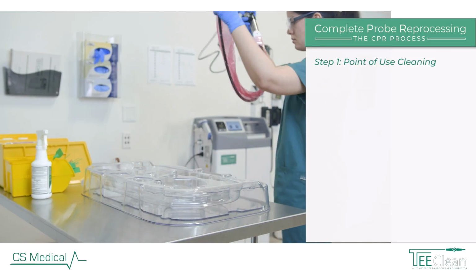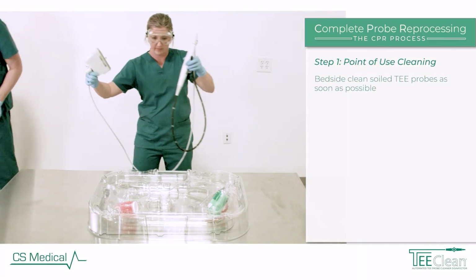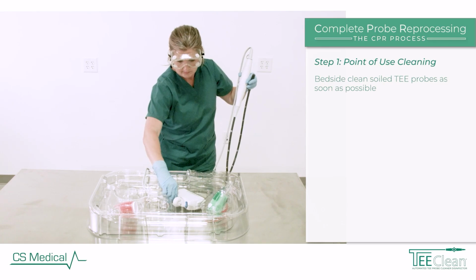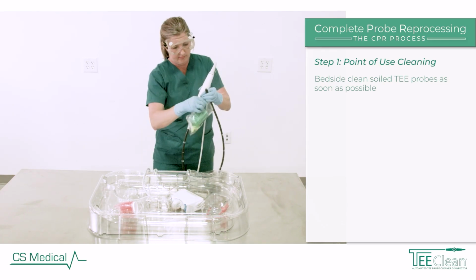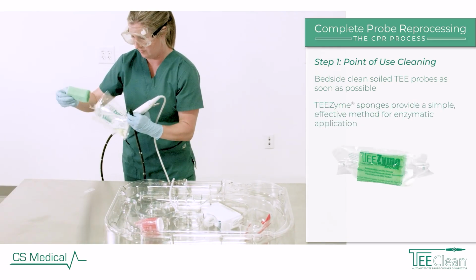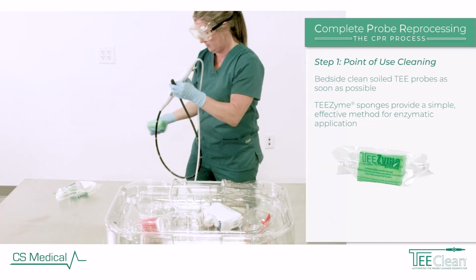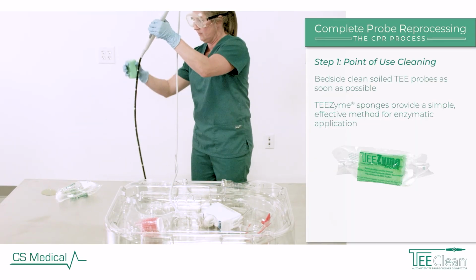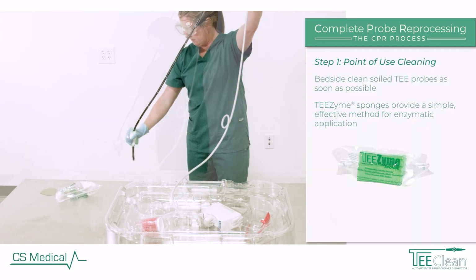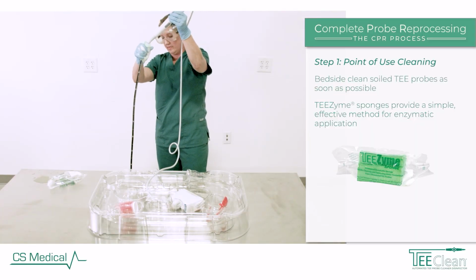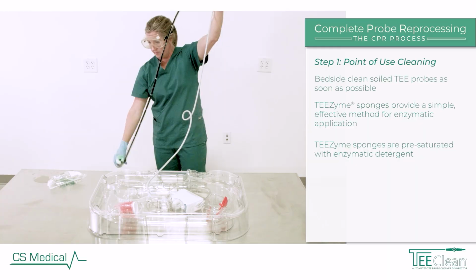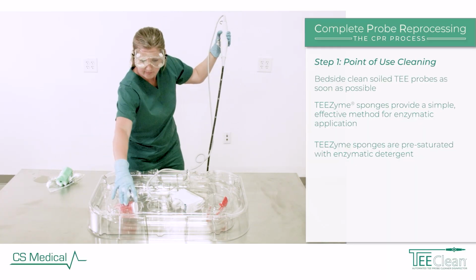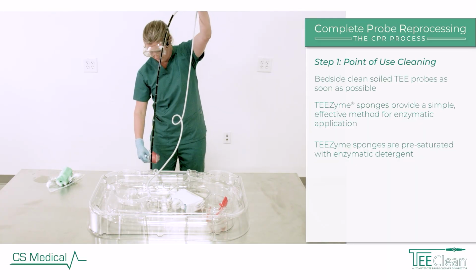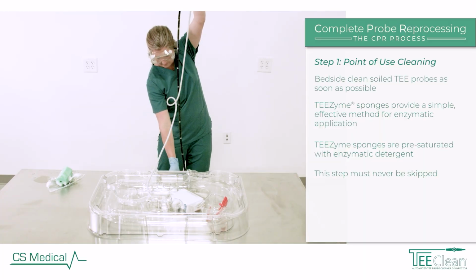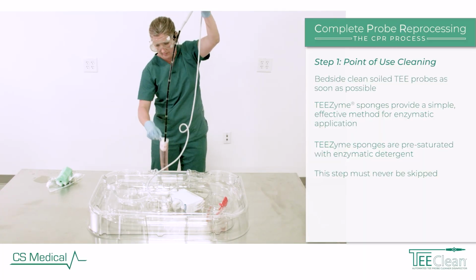Step 1. Point-of-use cleaning. Bedside clean soiled TEE probes as soon as possible once removed from a patient's esophagus. TEEZyme sponges provide a simple, effective method for enzymatic application to the TEE probe insertion shaft directly after removal from a patient's esophagus. TEEZyme sponges are pre-saturated with an enzymatic detergent to begin the process of breaking down bioburden. This step is extremely important in preventing the development of biofilm and must never be skipped.